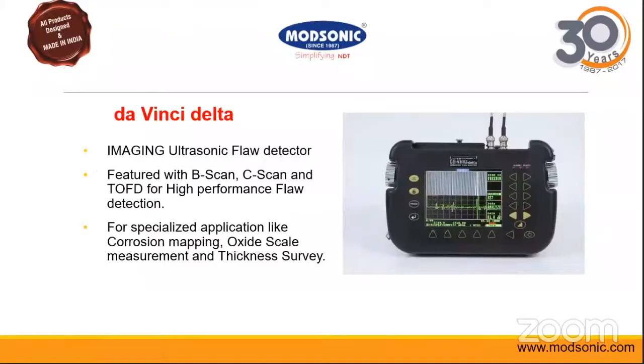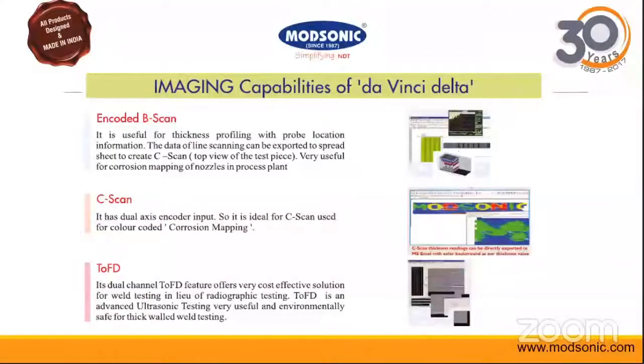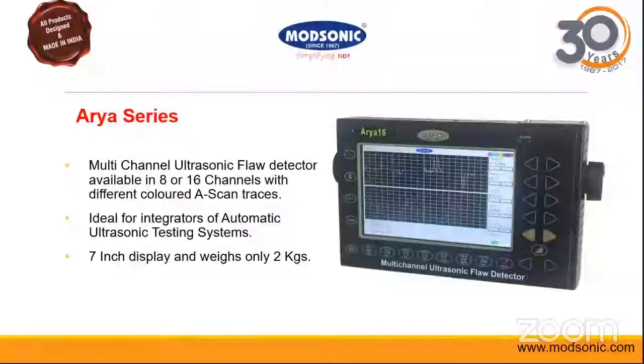The Da Vinci Delta offers B-scan, C-scan, single channel ToFD, and is a very good equipment with advanced functionalities, especially useful for corrosion mapping, oxide scale measurement, and thickness survey. Its features include encoded B-scan, C-scan, color B-scan, and single channel ToFD. We also have the Arya series multi-channel equipment in our portfolio for special or customized applications where multi-channel setups are required.